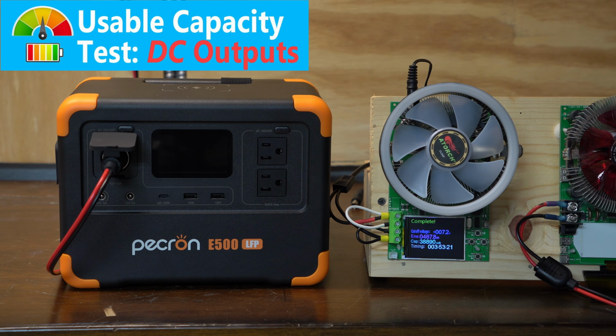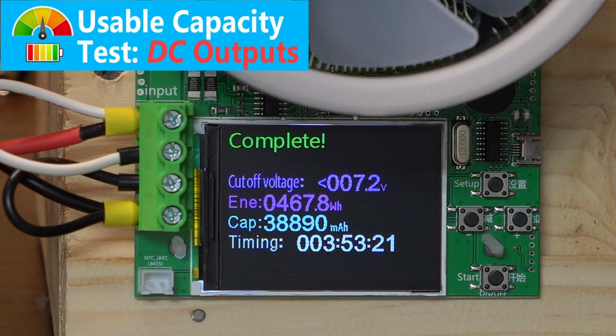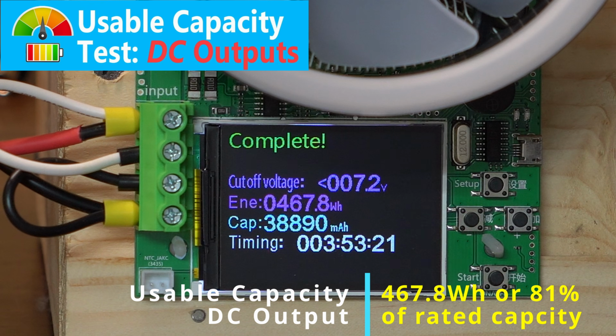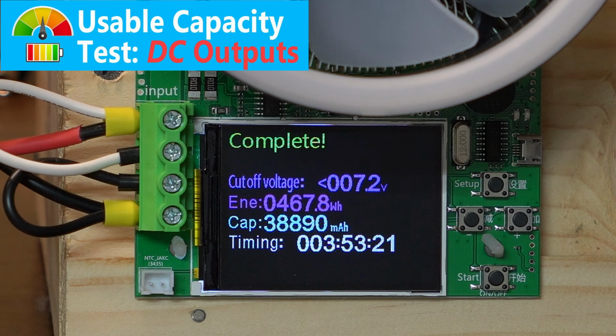All right, our DC discharge test is done. Let's zoom in here and see how we did. It looks like we got a total of 467.8 watt hours, out of 576, so that's just a little over 81%, which is pretty average. My average numbers typically fall between 80 and 84% on the DC discharge test with these particular testers.